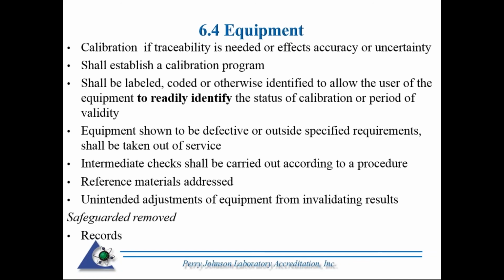Slight change here. Always specified in 2005, and it was that sort of disclaimer, whenever practical. So unless it was not practical, as an internal auditor or an assessor, you're looking for the calibration status to be on that equipment, i.e. labeled. 2017 basically states it has to be readily identifiable. Hence, you go up to equipment, a balance, a pipette, a thermometer that needs a calibration. It's not required that that label be on there. However, it's something that needs to be readily available.